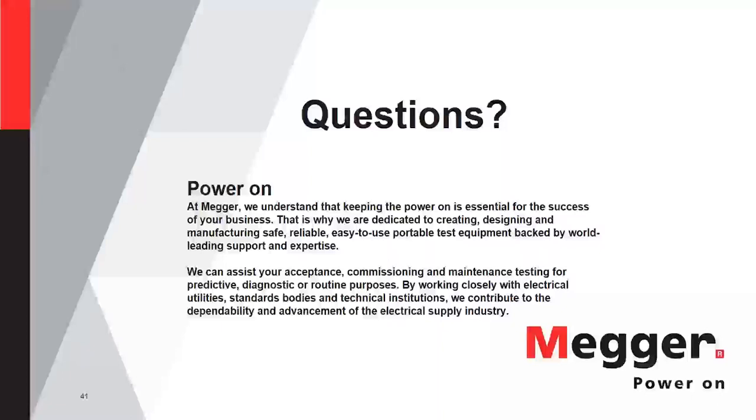So you would like to run the 8-hour test, but if you don't have that amount of time, the expectation is that the tables from the manufacturer will provide that equivalency between the discharge current and the discharge time. And actually, that is something that you might want to verify or confirm by running a test for 1 hour and later on running a test for 8 hours and seeing if you obtain the same capacity.